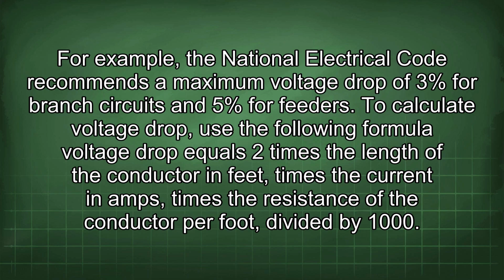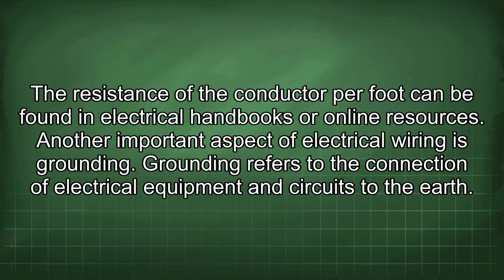To calculate voltage drop, use the following formula: voltage drop equals 2 times the length of the conductor in feet times the current in amps times the resistance of the conductor per foot divided by 1000. The resistance of the conductor per foot can be found in electrical handbooks or online resources.